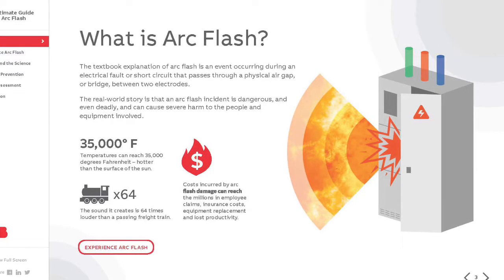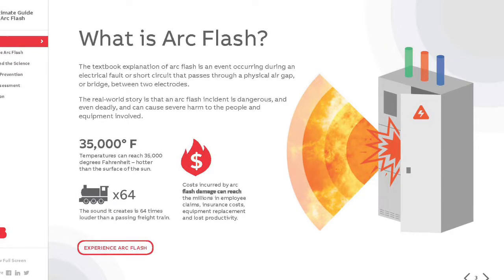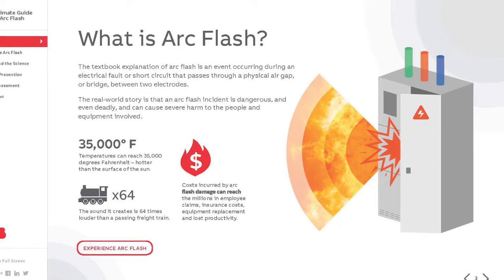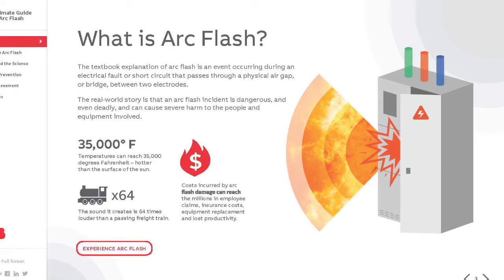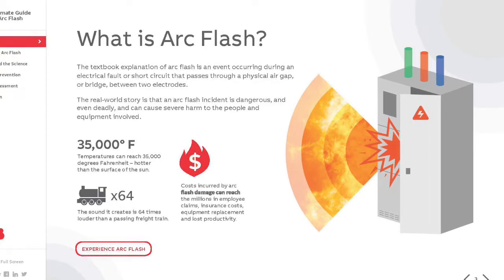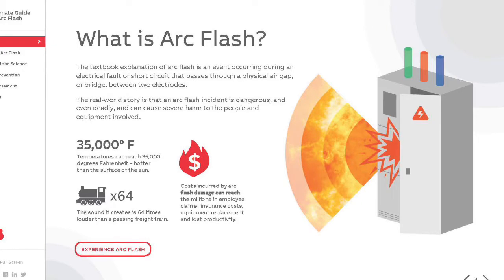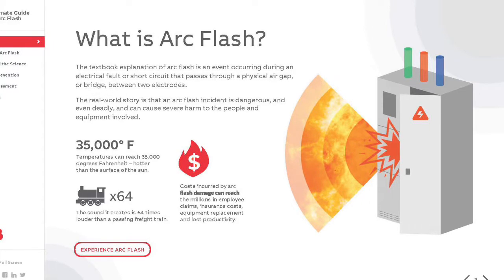Arc terminal temperature is estimated to be in excess of 35,000 degrees Fahrenheit — the surface of the sun is only 10,000 degrees Fahrenheit. The tremendous temperature of the arc causes the explosive expansion of both the surrounding air and the metal in the arc path. The superheating of the air during an arcing incident creates an acoustic wave similar to the generation of thunder by lightning.